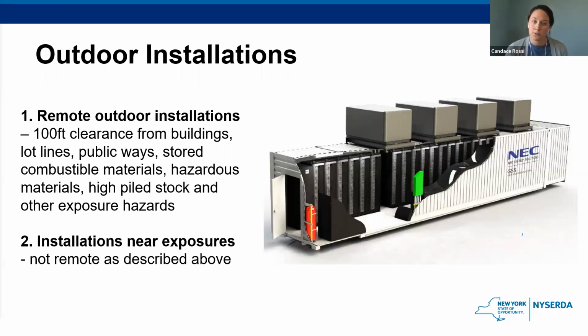So moving along, those were just the specific indoor installations. Now we're moving to the outdoor installations. Outdoor installations are defined as either being remote or near exposures. Remote outdoor installations are considered anything that has 100 feet clearance from buildings, lot lines, public ways, stored combustible materials, hazardous materials, high piled stock, and other exposure hazards. And installations near exposures is once again just not remote as described above.